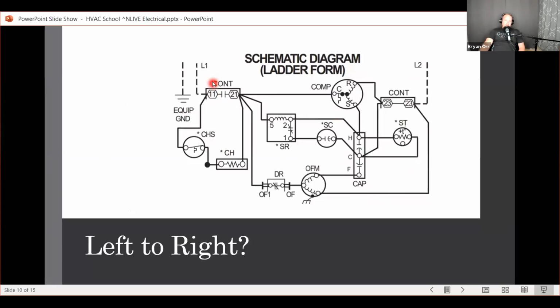This is a really interesting one anyway, but this is what happens: a lot of technicians will take a voltmeter and look to see if voltage is present. They will measure L1 and L2, or measure somewhere in the circuit, and find 120 volts to ground on both sides. In most cases they're going to have a misdiagnosis, because they're imagining it's coming from this side, when in reality it's just coming from the other side.